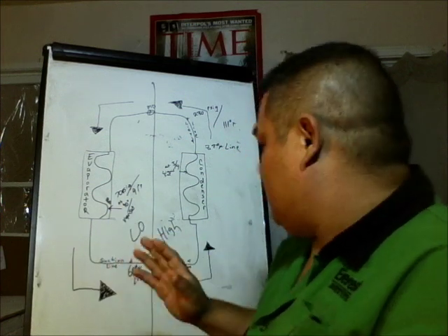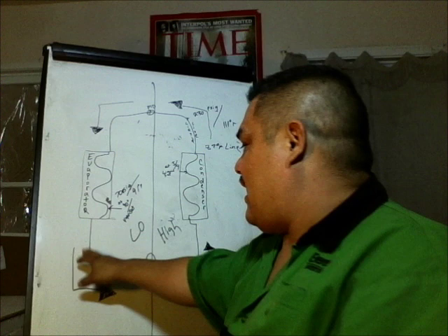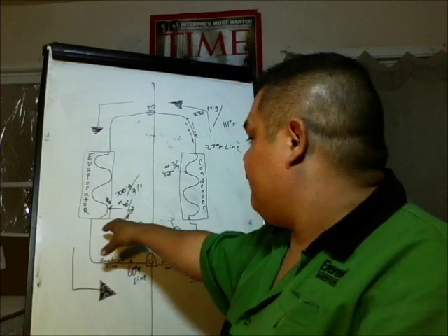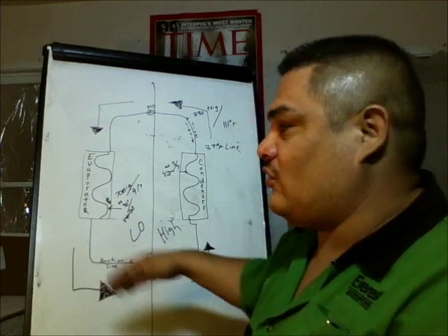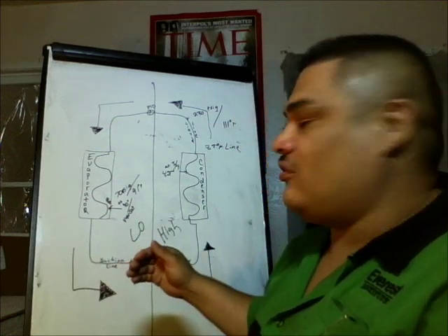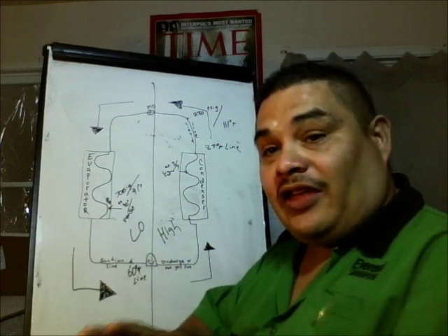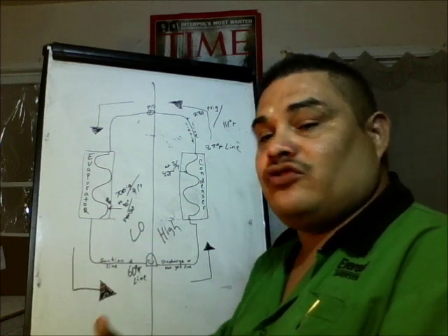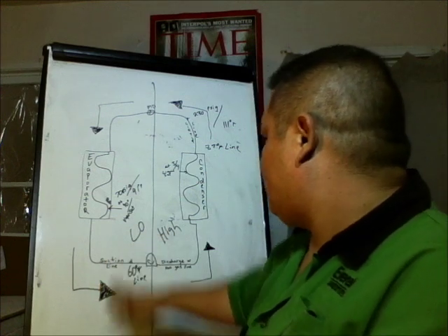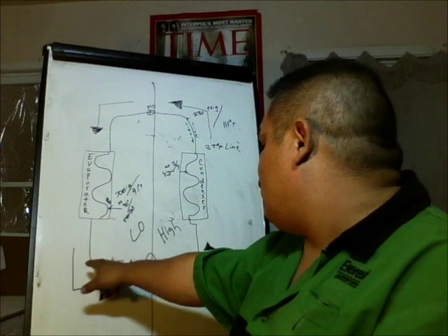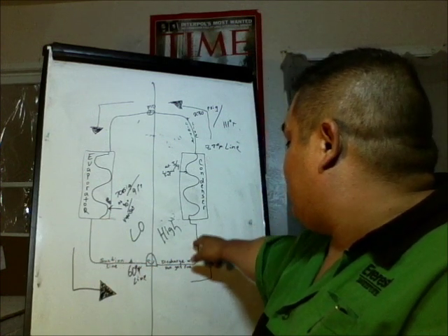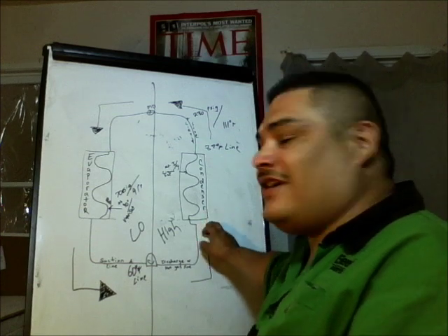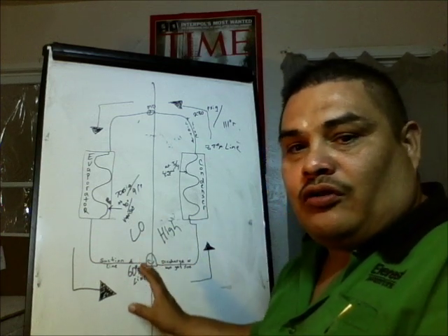That is the heat being added after you've already gone into the vapor. Now, again, this is sensible heat. This is when your temperature starts to rise on the thermometer. With that, you're going to be able to measure the amount of superheat, so we'll get to that in a minute. But going through the suction line into your compressor, through your hot gas line, entering into your condenser, that's where we no longer measure superheat.